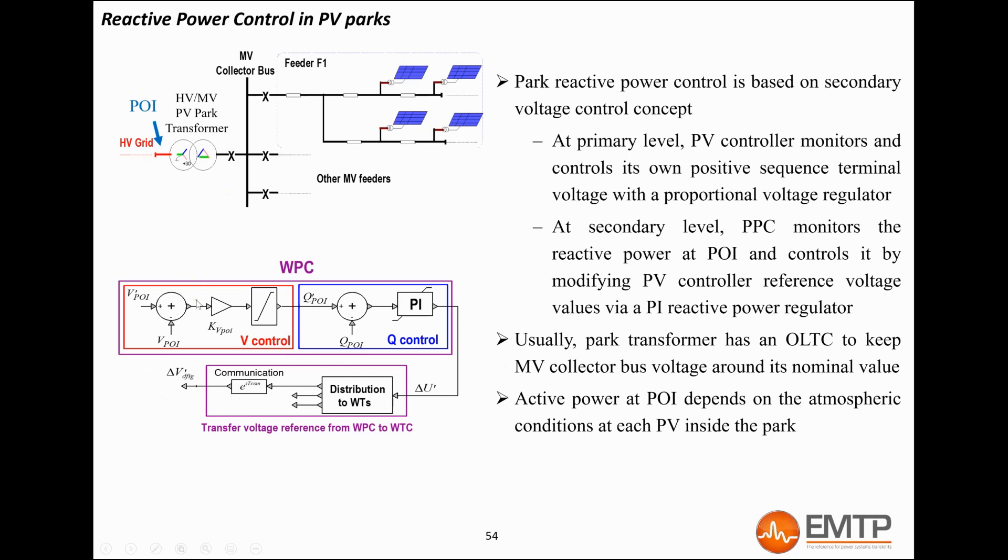In the case of the EMTP 4.1 generic model, only the park reactive power control loop of the PPC is modeled. To control the reactive power, the PPC sends a voltage deviation reference to all the PV controllers.